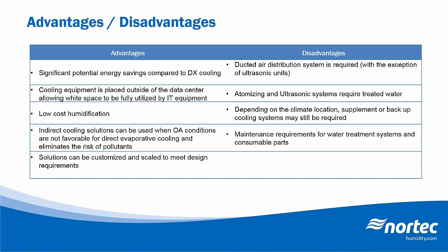So looking at some of the disadvantages here, in order to really apply an evaporative media system or an atomizing nozzle system, we do need a ducted air distribution system. So if it's a retrofit application or an existing data center, it may be difficult to find that room if there's no ducted system. And typically these systems do need a stainless steel wet section as well. So if there is a ducted section or an air handler, if you're doing a retrofit application, it may be difficult to find that amount of space to install the equipment itself.